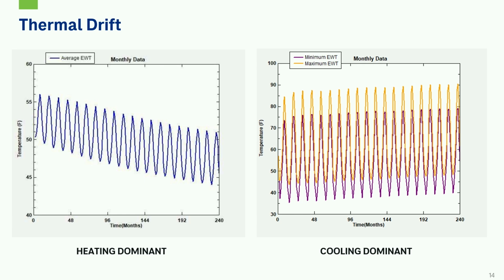So we're going to eventually keep making the ground colder, and we're going to have a lower entering water temperature as we go throughout the years. On the right, you can see this is now showing the minimum entering water temperature in that purple color, and then also the maximum entering water temperature instead of the average. Just wanted to clarify that in here. But this is for a cooling dominant system where you see that trending upwards, and we have more cooling load than we have heating load, so we're depositing or rejecting more heat into the ground than we are taking out to heat during the winter season.